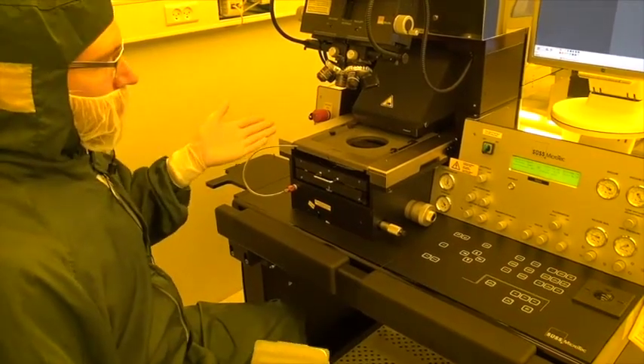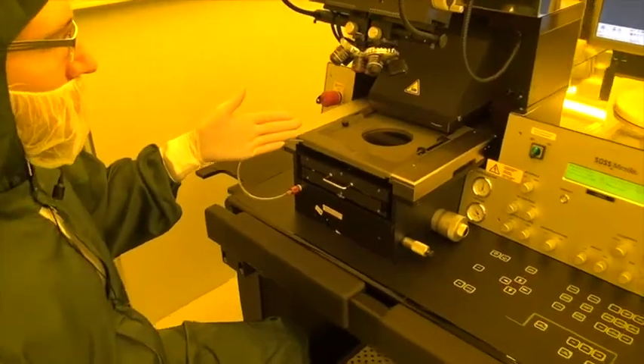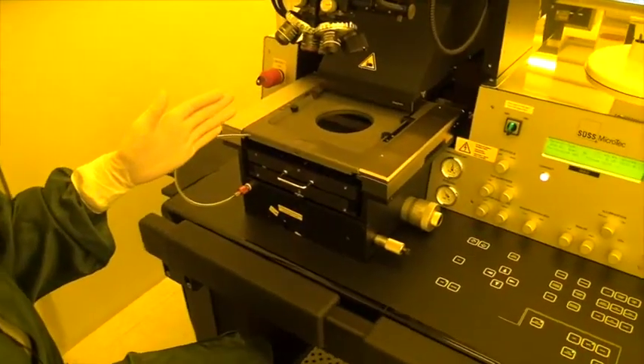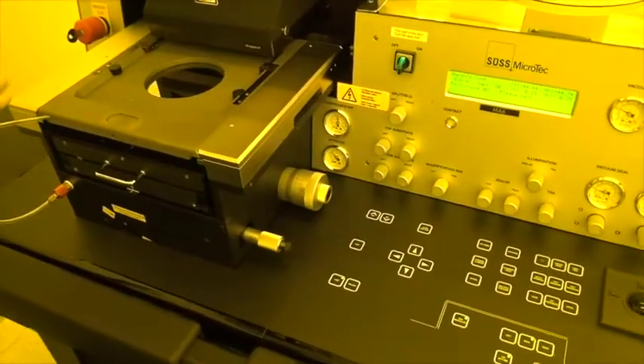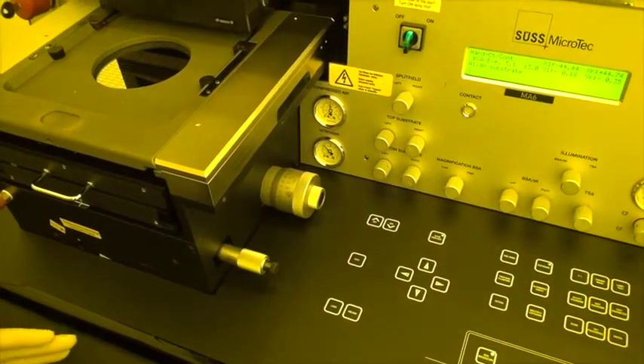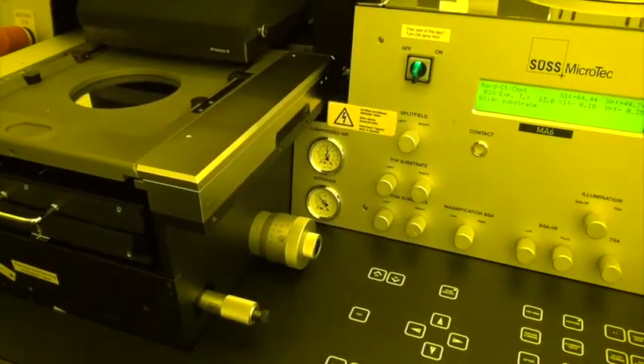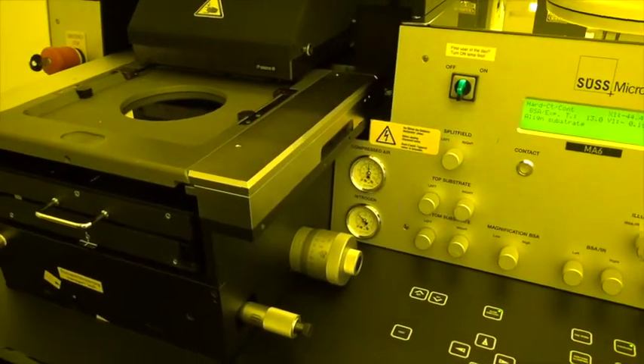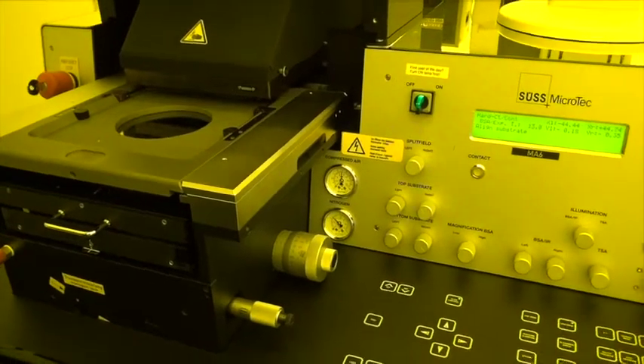Now the sequence is immediately to do the wedge error compensation. So this is carried out now and is followed by a pause which is intended for the alignment of the substrate. This also means that at this point if freehand alignment is necessary on the first print it can be carried out now.